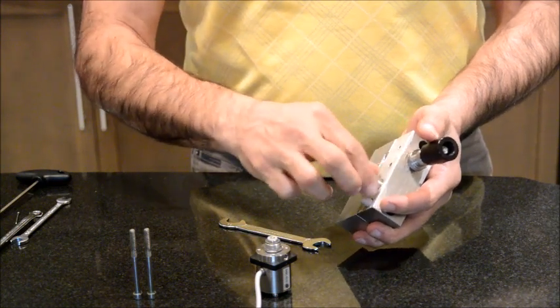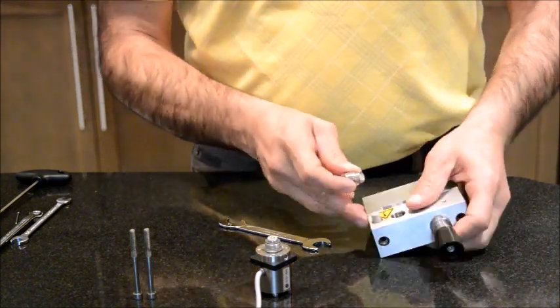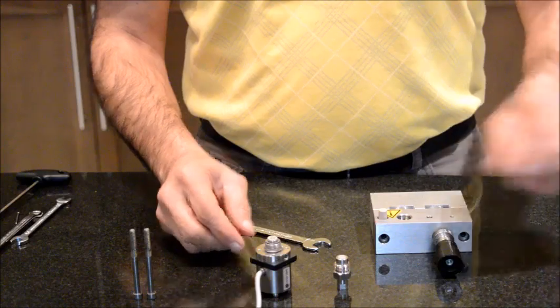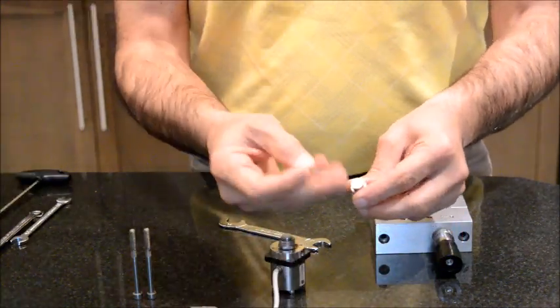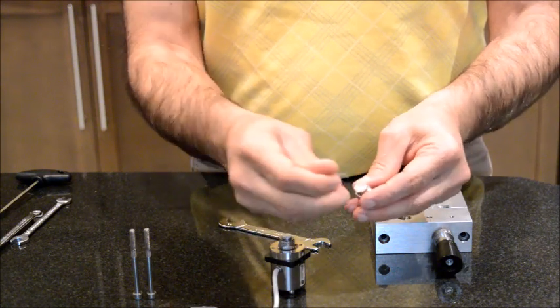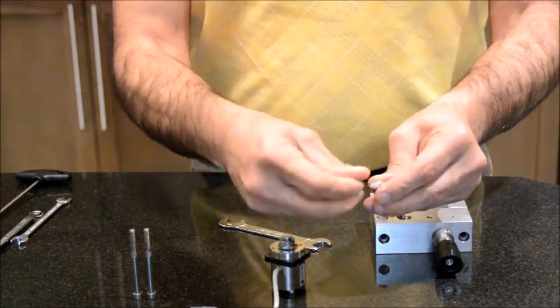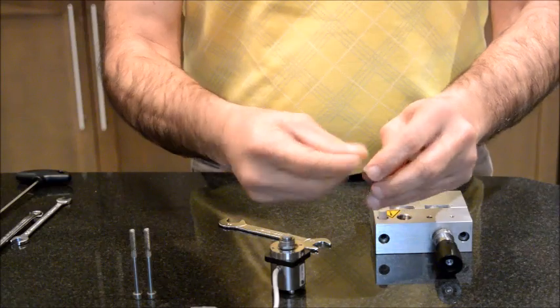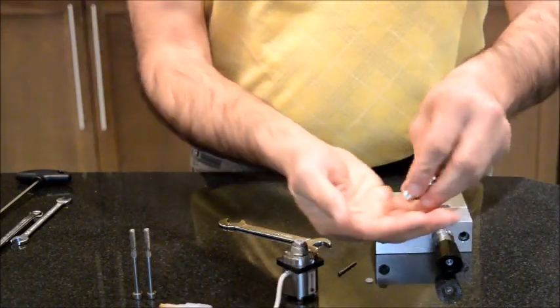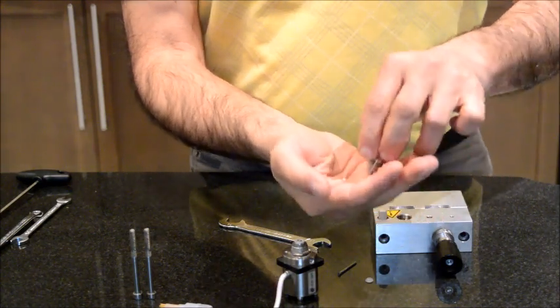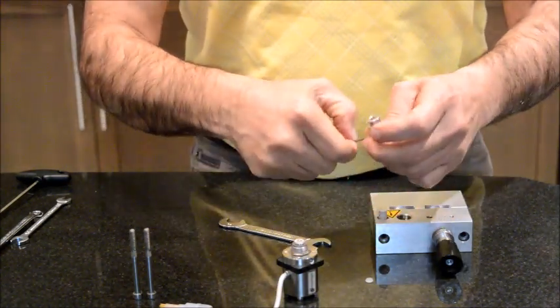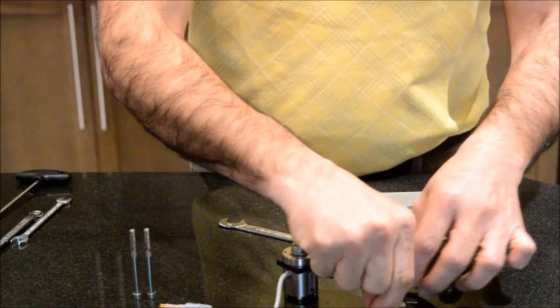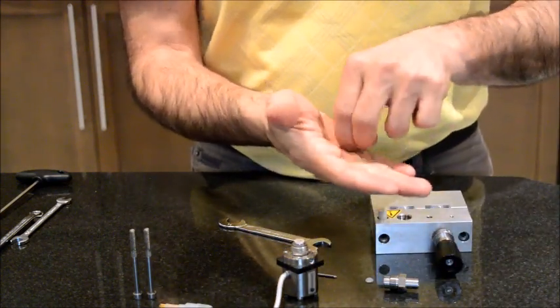Now as I said if you see that your pump is working but there is no flow or if the flow is fluctuating it's due to these valves. For the outlet valve I'm going to use a needle. You have to remove this piece of plastic and there is a part inside that you need to replace. So that's a replaceable part, consumable, you can buy them so you rebuild your outlet valve.